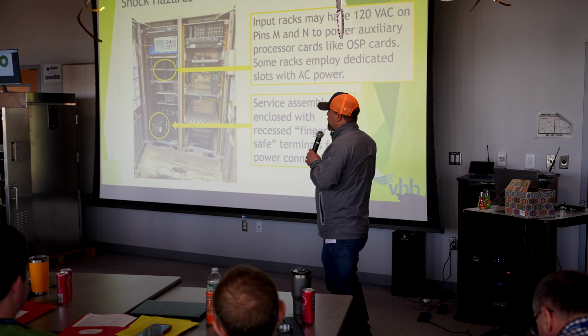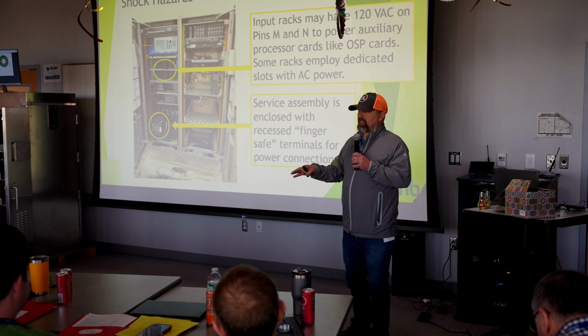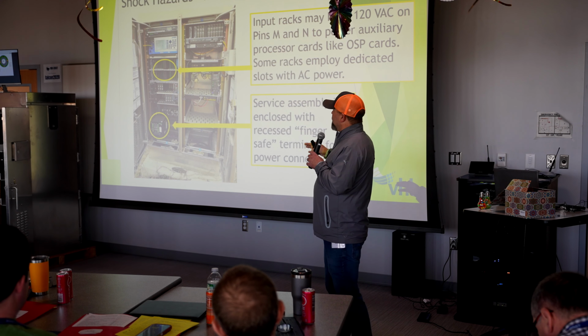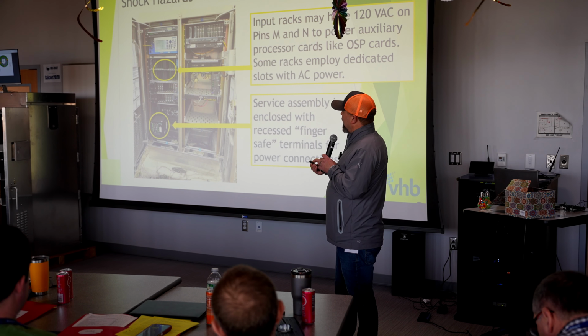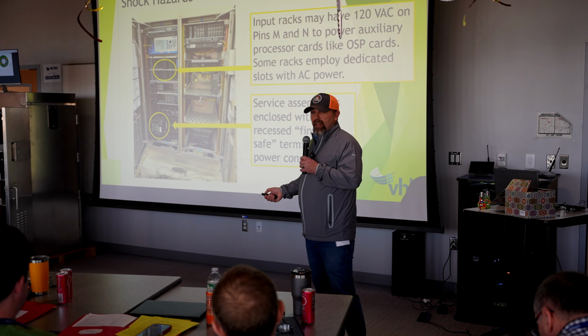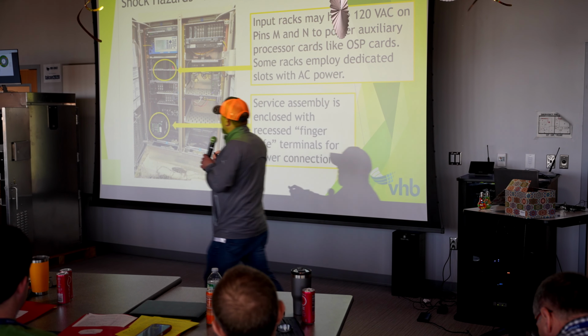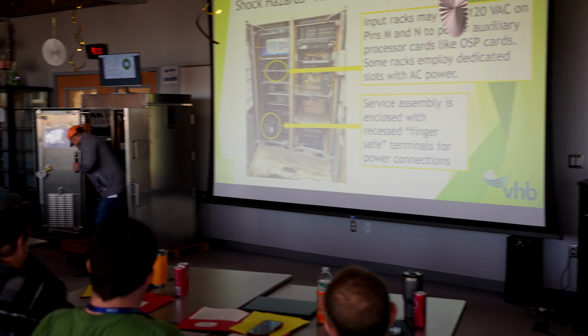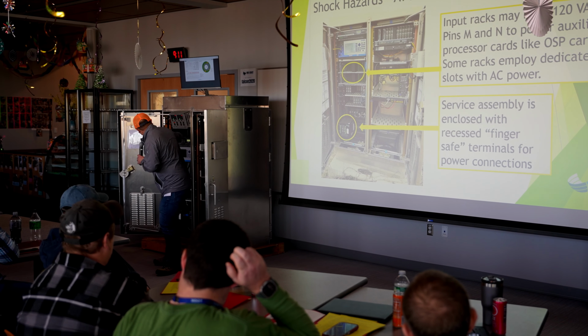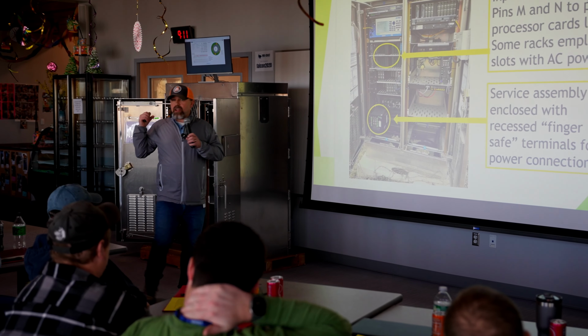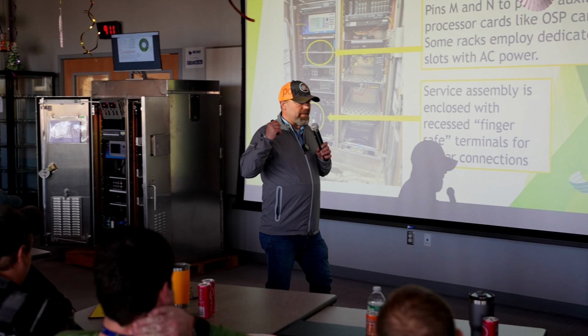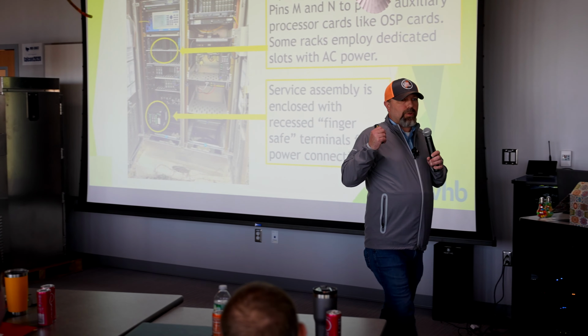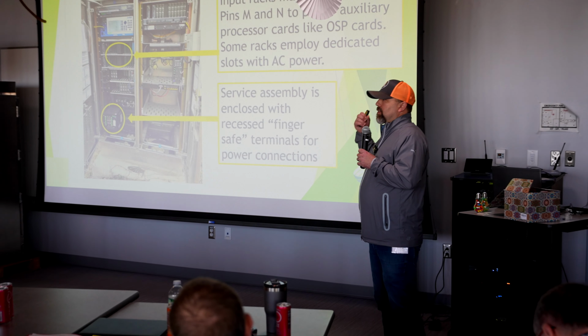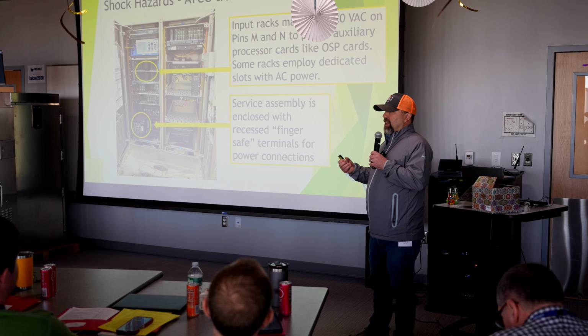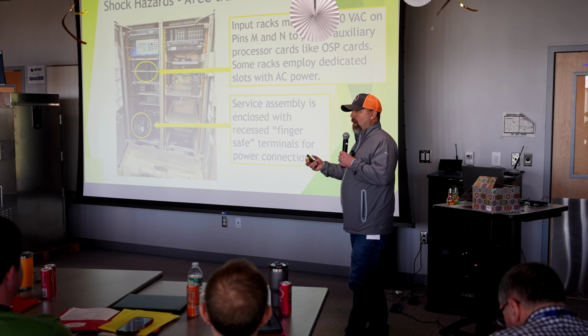The premise behind this is to make it as finger safe, touch safe as possible. But a lot of people may not realize that these input racks that live right here in the middle—up here—some of those racks will actually have 110 volts on the edge connectors. The reason for that is so that cards like Opticom cards, preemption cards, certain auxiliary cards, require 110 volts to operate.